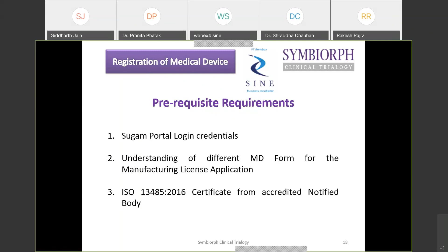So if it is an existing device and a predicate device is available in the Indian market, and if your device falls under class A or B, then you have to apply under form number 3, and you will be getting the permission under form 5. And if you don't have a manufacturing facility, and you are relying on another facility to manufacture your devices, then under the loan license you have to apply in form number 4. And if your devices fall under C and D, then for the manufacturing license you have to apply in form number MD7, and for the loan license in MD form number 8.